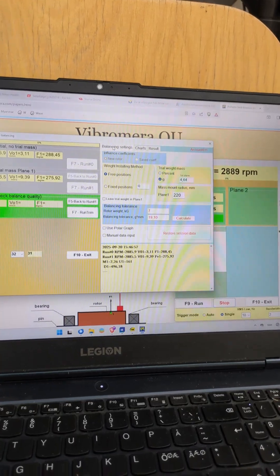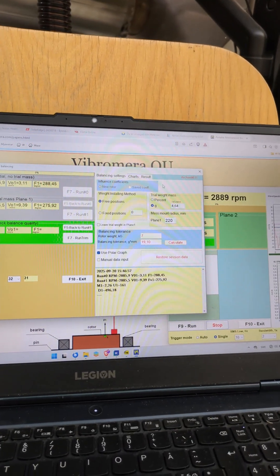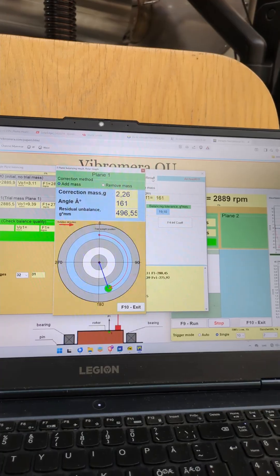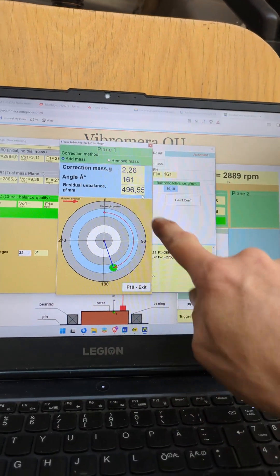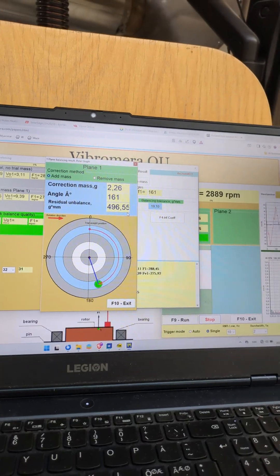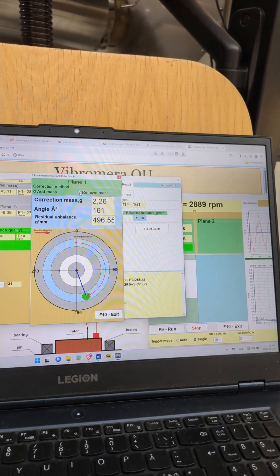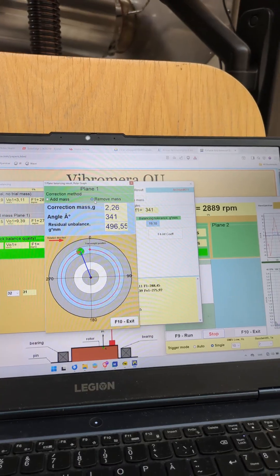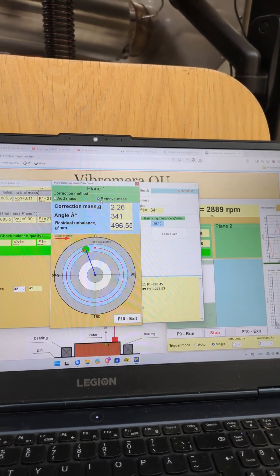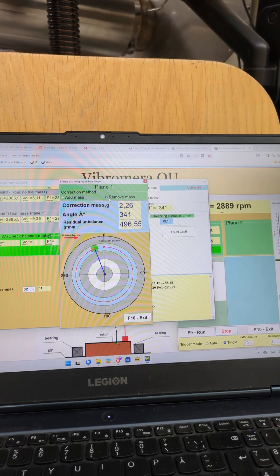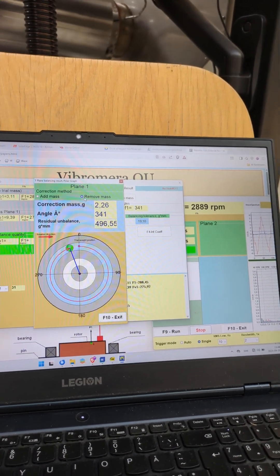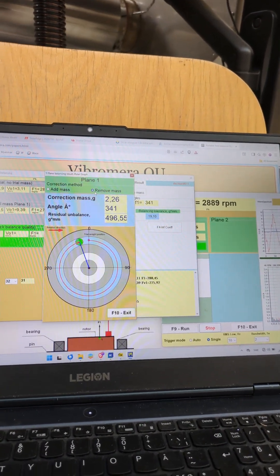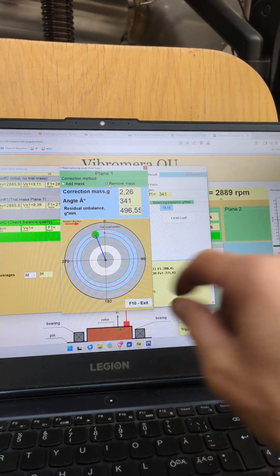Now we go back to settings and use polar graph and the nice thing here is that then you'll get to know in the rotation direction where you're going to do the correction. In our case we're going to remove mass rather than adding mass because the fan will look much prettier that way. 2.26 gram at 341 degrees in the direction of rotation.